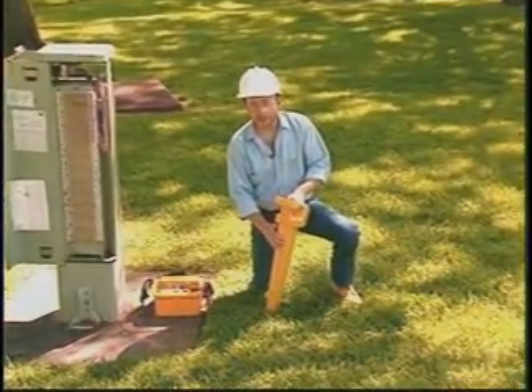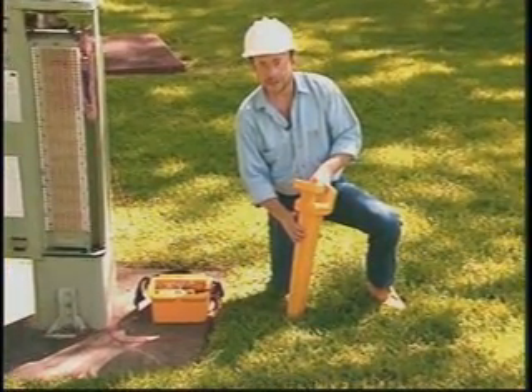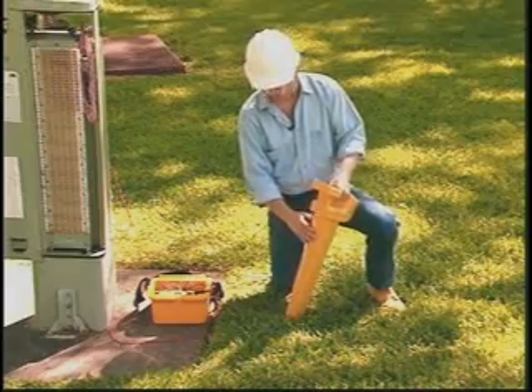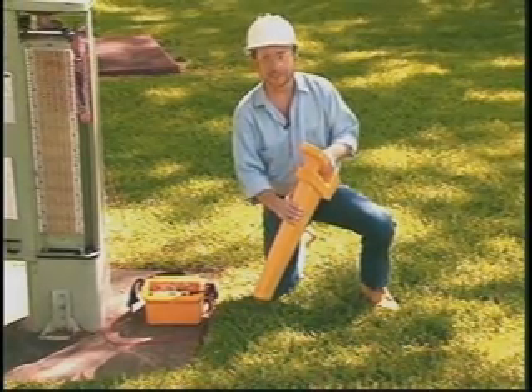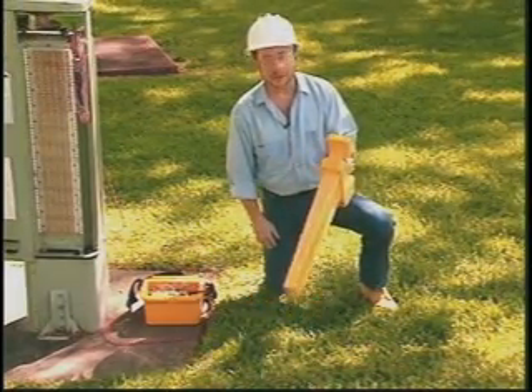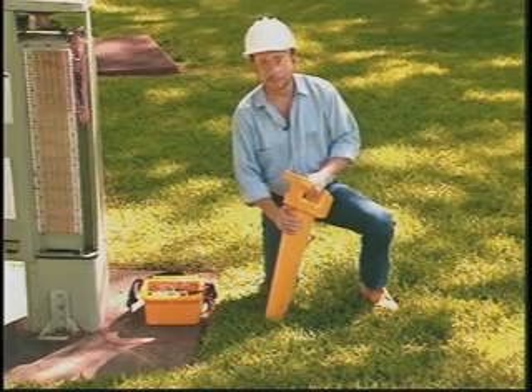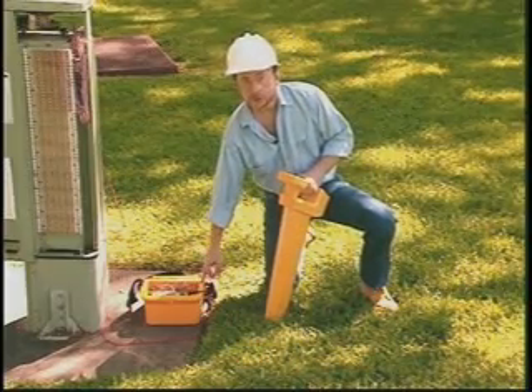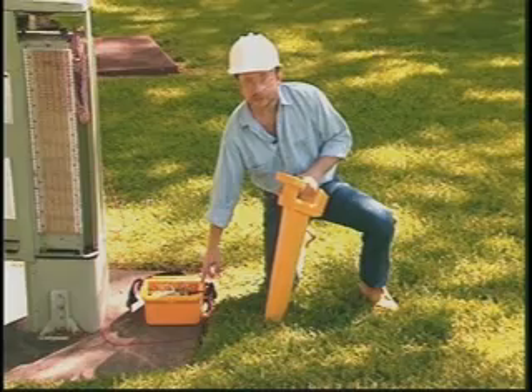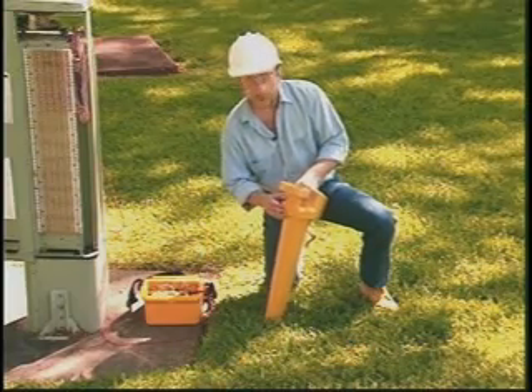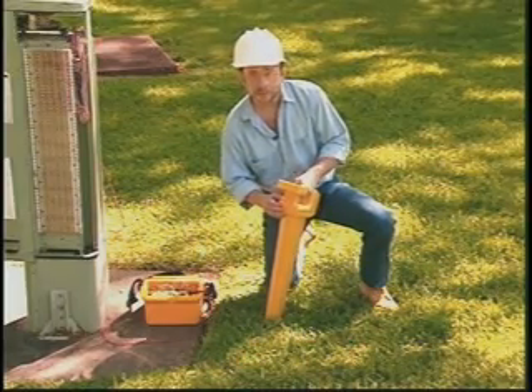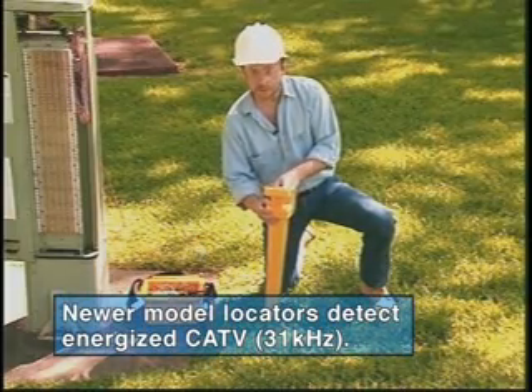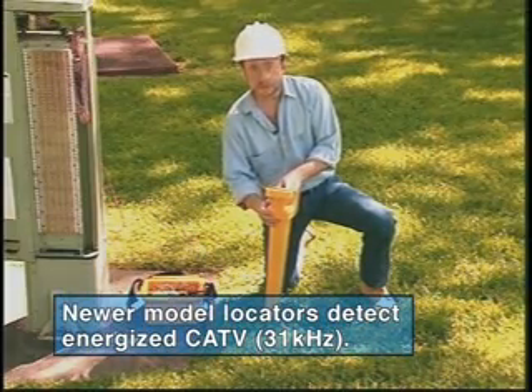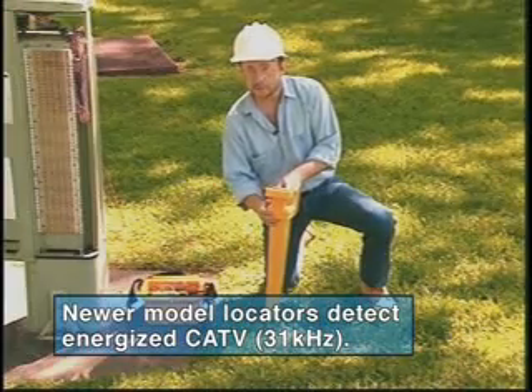This is the Dynatel2273 Advanced Cable and Fault Locator. It's rugged, water resistant, it's lightweight, well balanced, and it's easy to operate. The transmitter is used to apply a signal to the conductor you want to locate. The receiver is used to trace the path of the signal. Now, in addition to detecting the transmitter signals, the receiver can also detect signals from energized power cables.